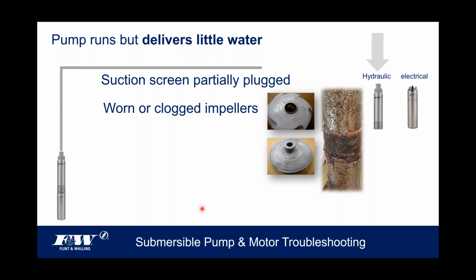And then again, we're going back to the pump end of this thing. If it's delivering very little water, there may be something going on inside with the impellers and the diffusers. Again, these things can clog. They can wear out. The images on the screen here would be an indication of a pump that was subject to some fine sand. Hopefully with these images, you can see the damage that can be created by sand in a submersible well pump. You start to erode material away, which is what's happening here, and your efficiencies and performances are going to drop off shortly thereafter. So it could be worn impellers.